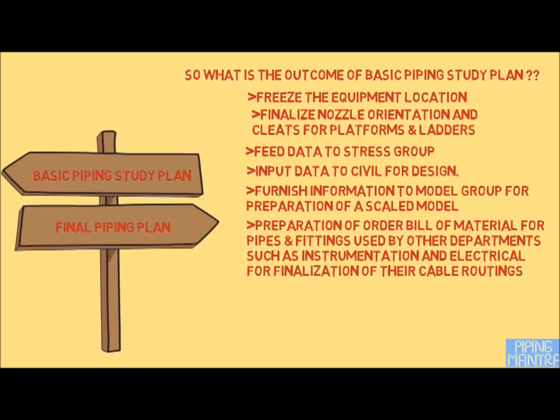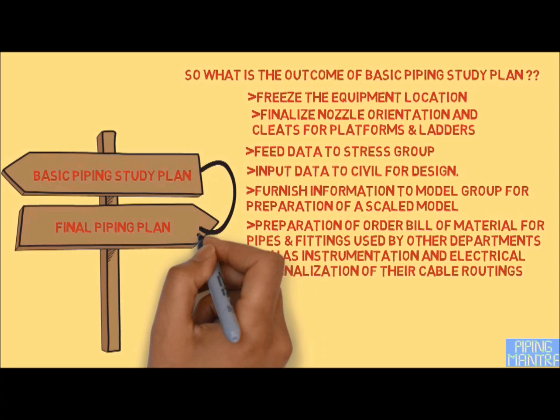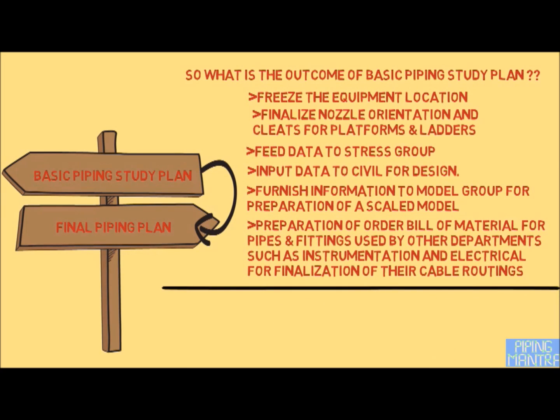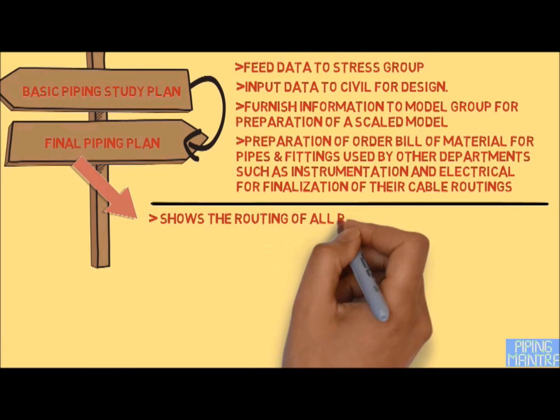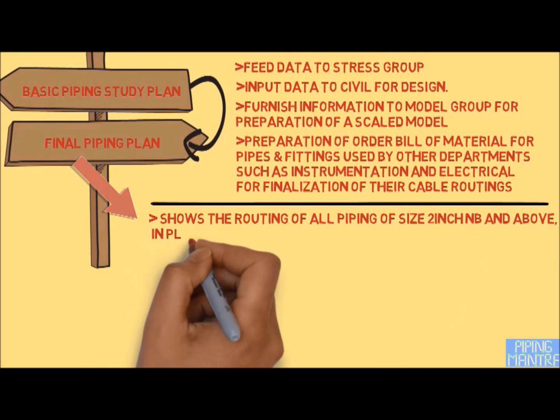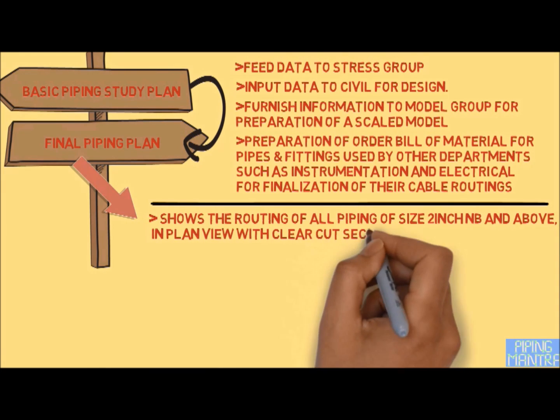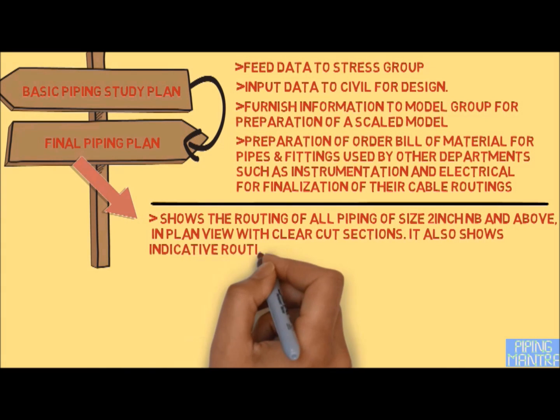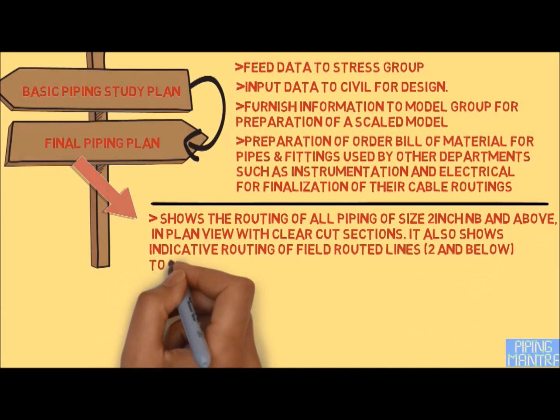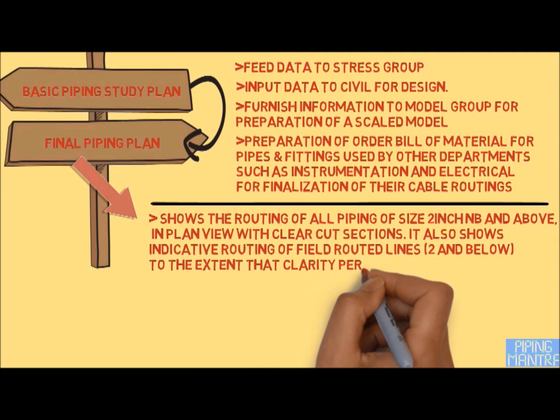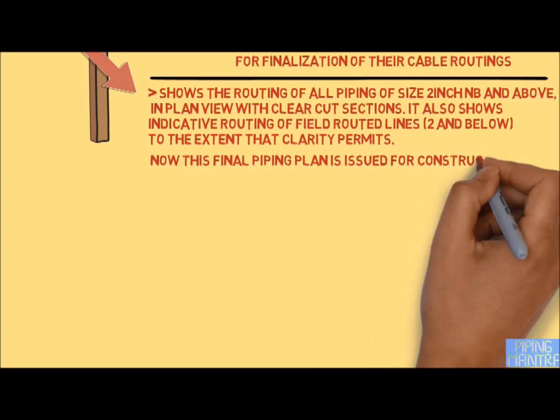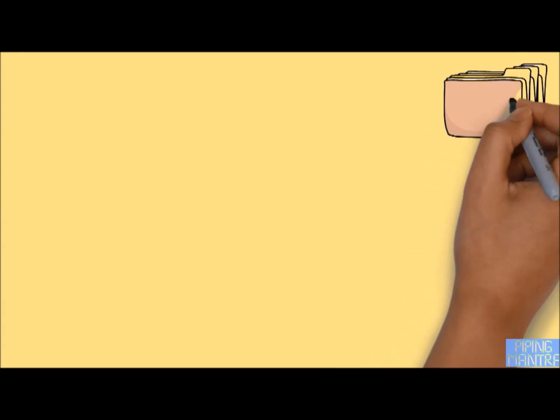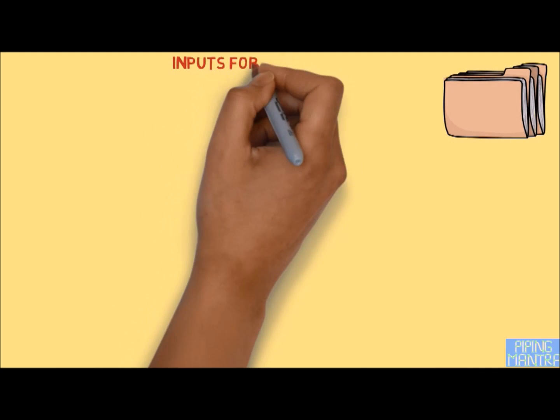We also furnish information to the model group for preparation of scale models whenever required, and prepare order bill of materials (MTO) for pipe fittings used by other departments such as control systems and electrical for finalizing cable routings. Piping plans are updated after receiving comments from other departments. The basic piping study plan, once frozen, becomes the final piping plan, showing routing of all piping of 2 inch and above in plan and sectional views. Below 2 inch lines may also be shown if clarity permits.